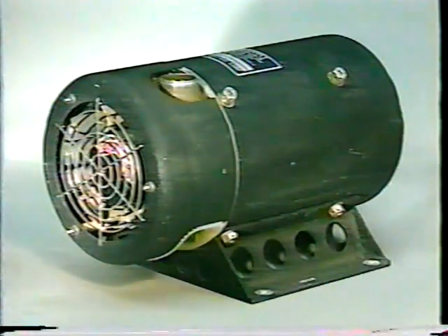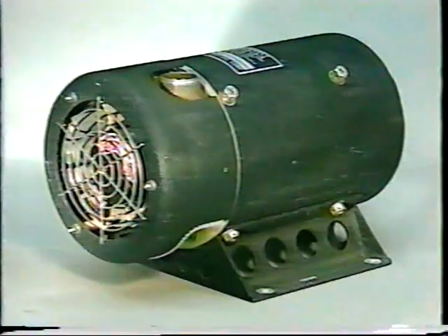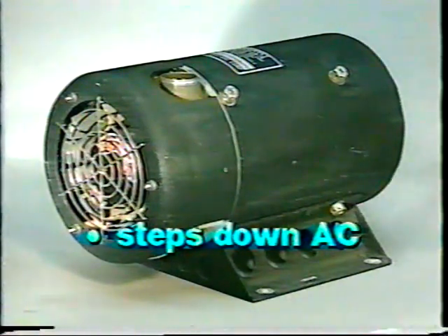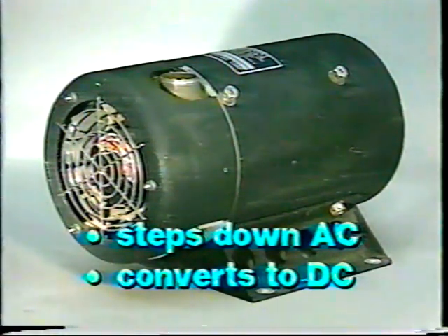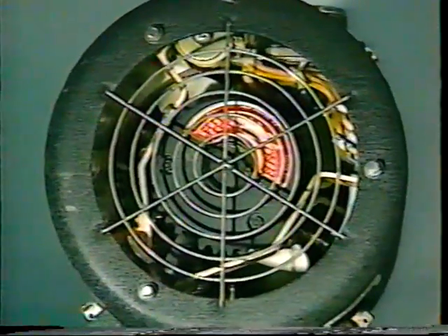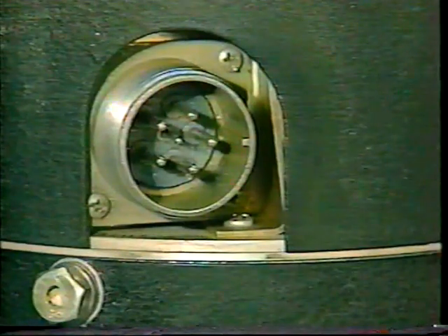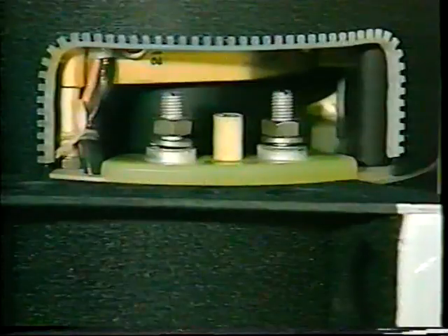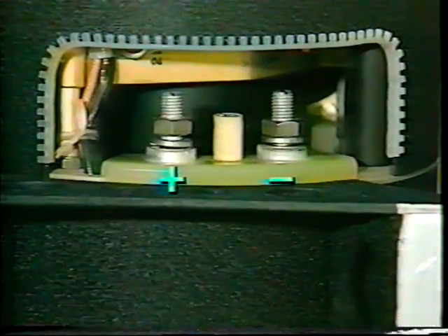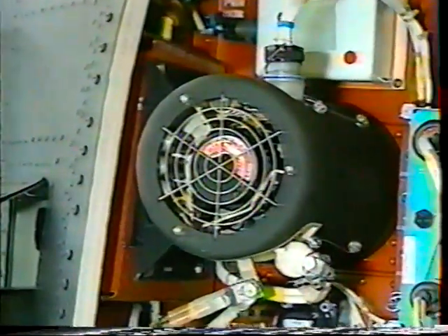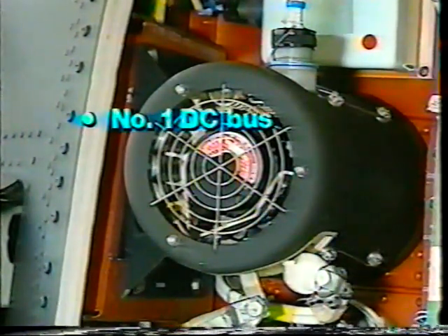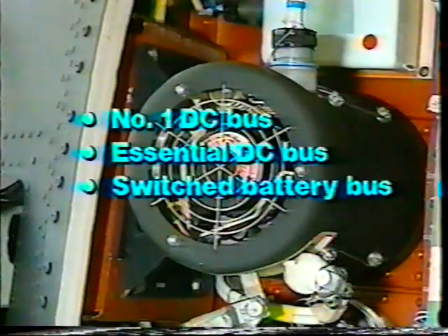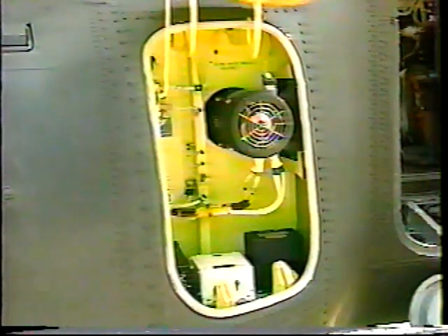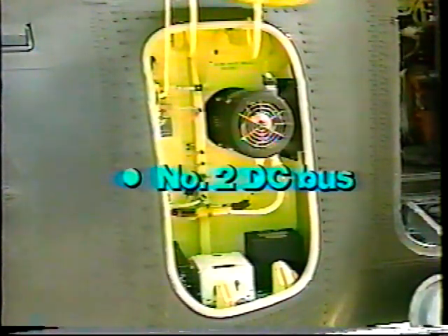The transformer rectifier units, or TRUs, operate off 200 volts, 3-phase AC. The transformer in each TRU steps down the 200 volts to 48.5 volts, 3-phase AC. 6 rectifiers convert the 48.5 volts AC to 28 volts DC. Inside the TRU is a cooling fan operated by AC. An AC quick disconnect input connector is located on top of the TRU with positive and negative output terminals located underneath. The number 1 TRU, located in the left electrical compartment, powers the number 1 DC bus, the essential DC bus, and the switched battery bus. The number 2 TRU, located in the right electrical compartment, powers the number 2 DC bus and the essential DC bus.